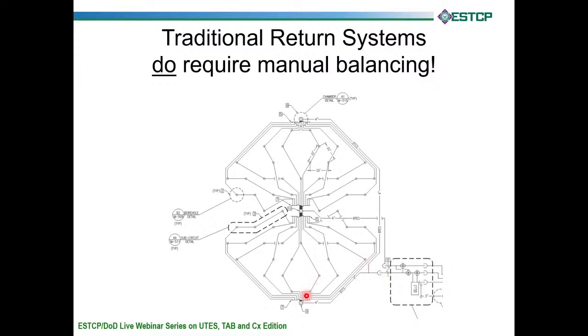So in this design, you have to have a TAB contractor go down in each of these vaults and balance these manual balancing valves. And it's very typical of what a TAB contractor would do, nothing that they would be unfamiliar with. One thing I do want to mention is that in these vaults, if you're designing this, you have to design these manual balancing valves to be bidirectional. And there are a few balancing valves that have those capabilities, but you do want to ensure they are bidirectional.